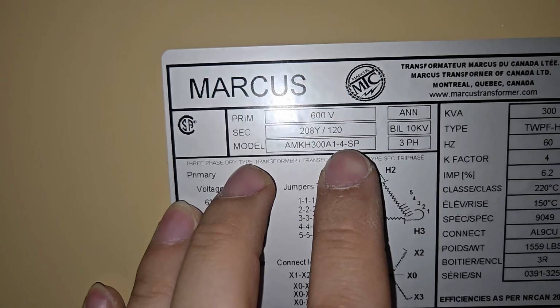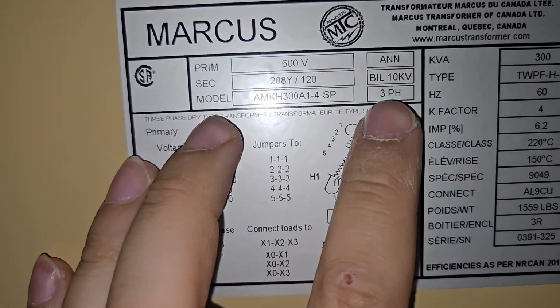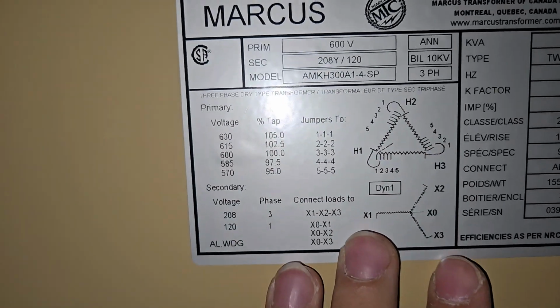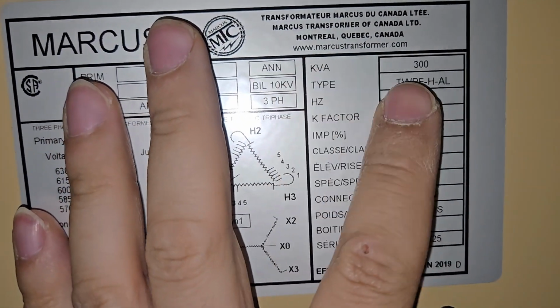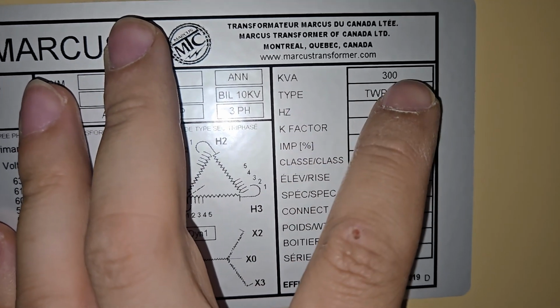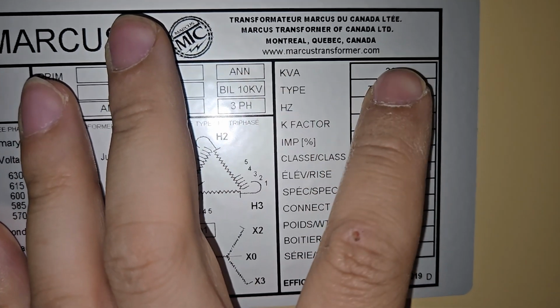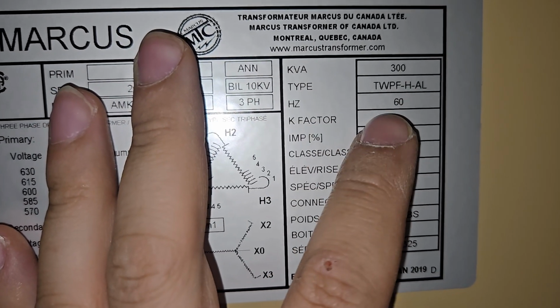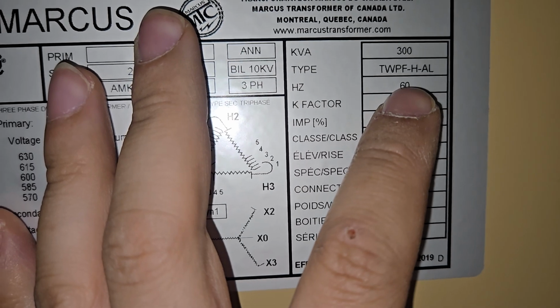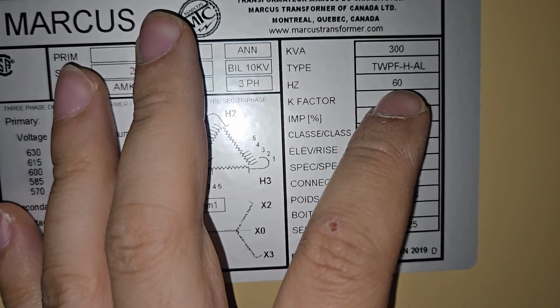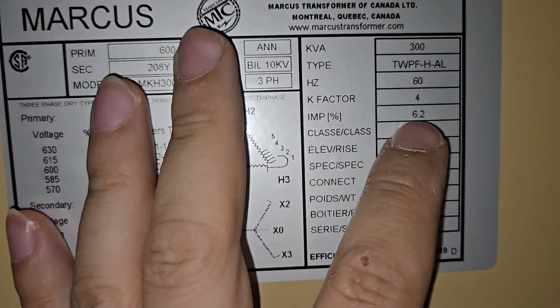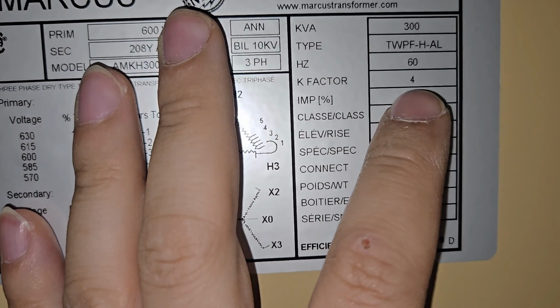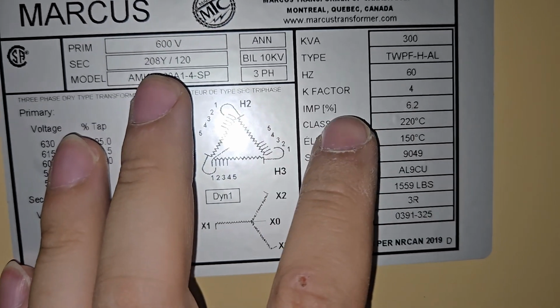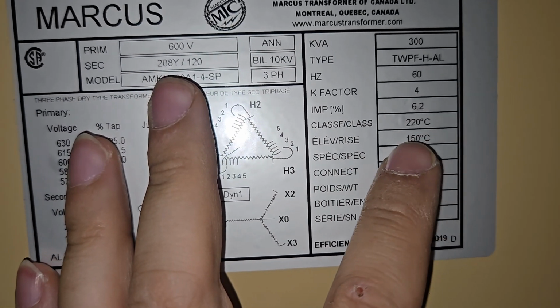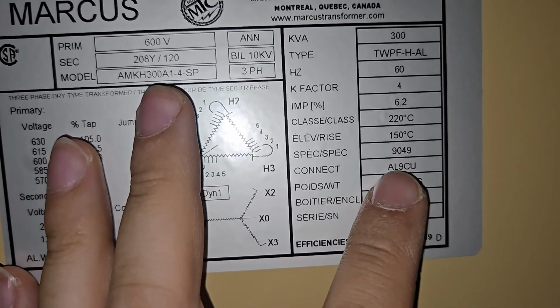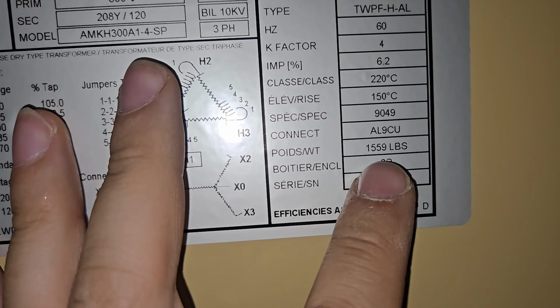And then you see the model, and this tells you the phases, so it's 3 phases. And then over here we can see what it's rated for. So it's rated for 300 kilovolt amps. That's how much power you can do. So you gotta pick a transformer that's rated for the amperage that you want, otherwise you will melt the transformer. And then it tells you the hertz, the K factor, which is suitable for certain types of location, and impedance, the class, the temperature rise, what you can use for connection, and then the weight.